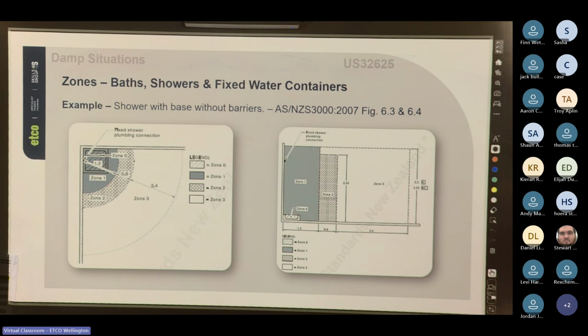So basically what they're saying is most of the time a fixed shower head can spray out to 1.2 meters. And then again, still 2.25 for New Zealand, 2.5 for Australia. Zone 2 is still, we will get to that. So yeah, then zone 2 is still 0.6 meters away from zone 1. And then zone 3 is 2.4 meters out from zone 2.